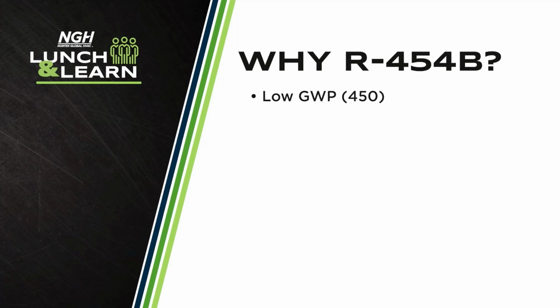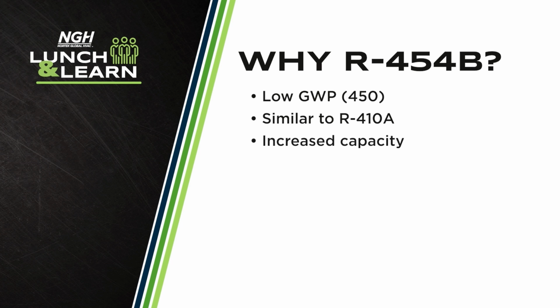So, in addition to being a greener and more environmentally friendly refrigerant, we believe R454B will also last longer in the market as GWP limits may continue to lower. This means less turnover of our product line and fewer model numbers for our customers to remember. Another reason our team decided R454B was the right refrigerant was its similarity to R410A. Both refrigerants operate at similar pressures, which will make the transition easier for users. R454B also provides a slight increase in capacity over R410A, so the new refrigerant allows systems to have a 10 to 20% smaller refrigerant charge than an equivalent R410A system. All this proves R454B is the right solution for NGH.